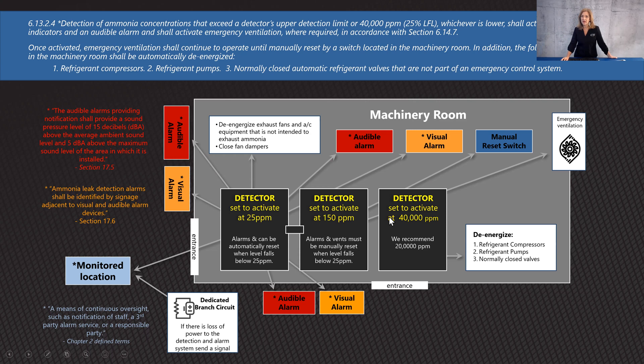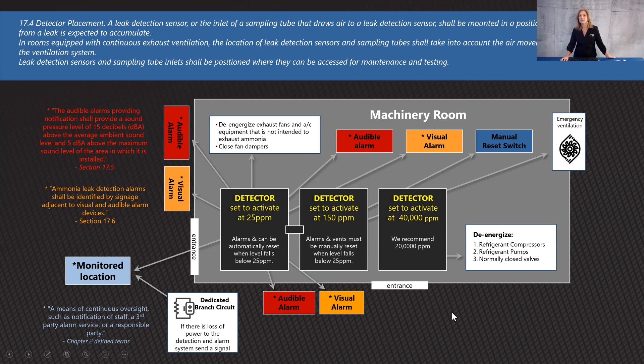Once you hit a 40,000 ppm measurement, nobody will be able to get into that room — it will be unbearable and dangerous, and there's risk of explosion. So in addition to signaling alarms and turning on emergency ventilation, you also have to de-energize anything that could cause a spark. The actual code quotes and references are available if you want to look those up.